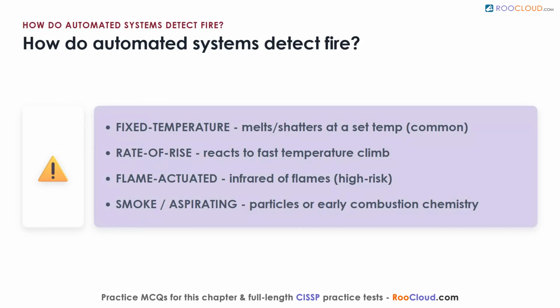How do automated systems detect a fire? Each type keys off a different sign of combustion. A fixed temperature detector, the common sprinkler head, triggers when a set temperature melts or shatters its element. A rate of rise detector reacts to how fast the temperature climbs, though winter heating can fool it. A flame-actuated detector senses the infrared signature of flames, fast and reliable but pricey, so it guards high-risk spaces. A smoke-actuated detector watches for particles blocking light or ionized air across a gap. And an incipient or aspirating detector sniffs out the chemistry of combustion before anything is even visible, the earliest warning and the most expensive. Whatever you choose, place detectors everywhere, including drop ceilings, raised floors, ducts, and shafts.